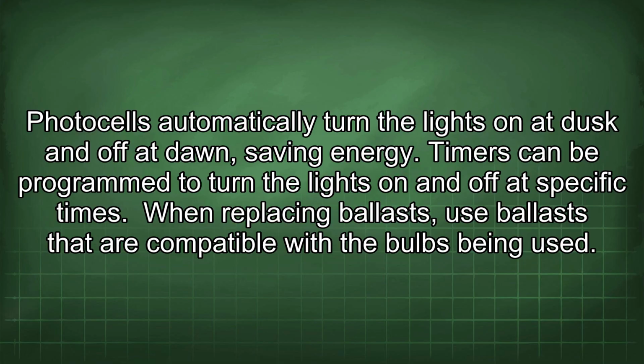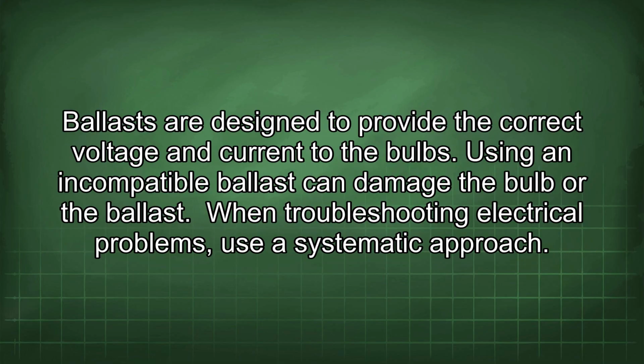When replacing ballasts, use ballasts that are compatible with the bulbs being used. Ballasts are designed to provide the correct voltage and current to the bulbs. Using an incompatible ballast can damage the bulb or the ballast.